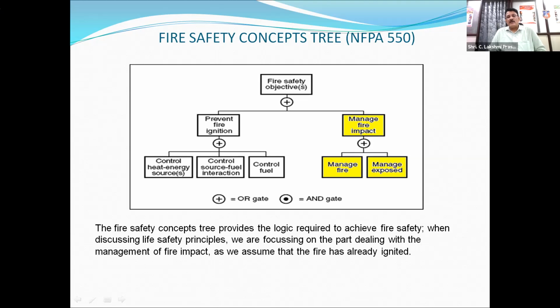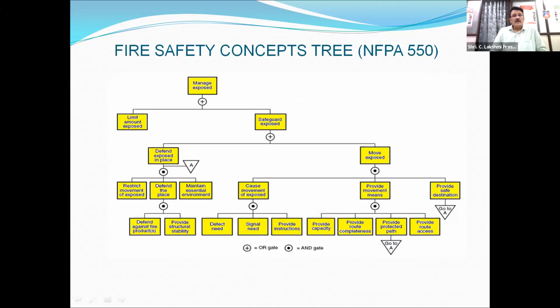And if we are unable to prevent the fire, then when fire occurs, we have to manage two things. We have to manage the fire, and we have to manage the exposed. Then in the fire safety concept, when we are trying to manage the exposed, they have given how we should manage: limit the amount exposed, or safeguard the exposed. There are these two options. In safeguarding the exposed, we defend the exposed in place. Like in hospitals, where the patients cannot help themselves. They are non-ambulatory, they are on various life safety gadgets. So there, the evacuation of the people vertically is a Herculean task. You cannot do that. So we have to defend them in place by moving them to the adjacent fire protected compartment.